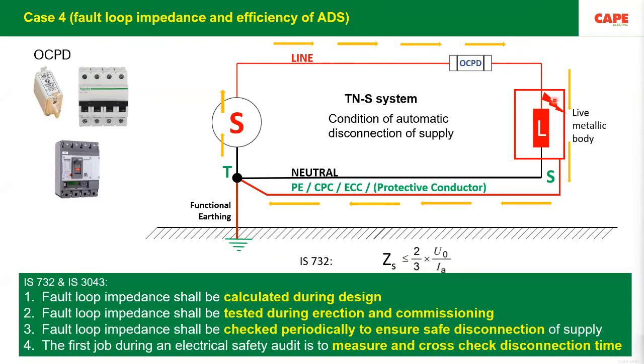So it means you have to have a meter. Nowadays, very good meters are available. You have to connect the meter into the circuit and put it on the test mode. One of our previous webinars was on the testing of this fault loop impedance. We can also send you the link of those videos, which explain how to make this particular test. Now I am trying to explain one of my experiences recently in Kerala.